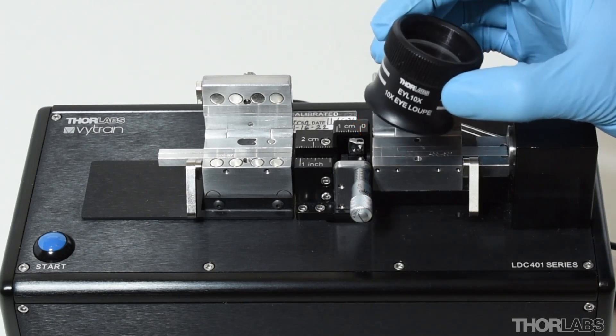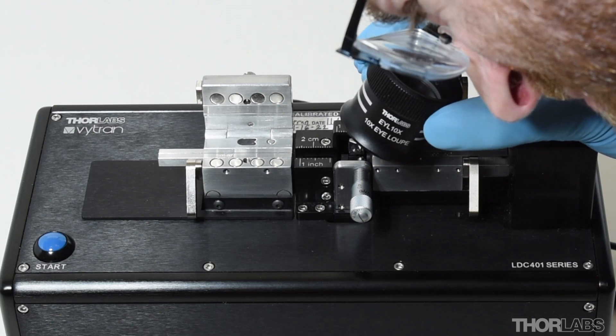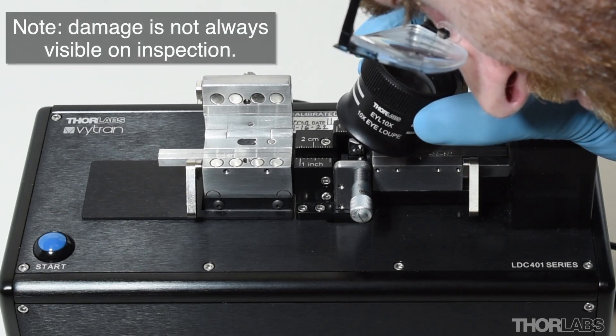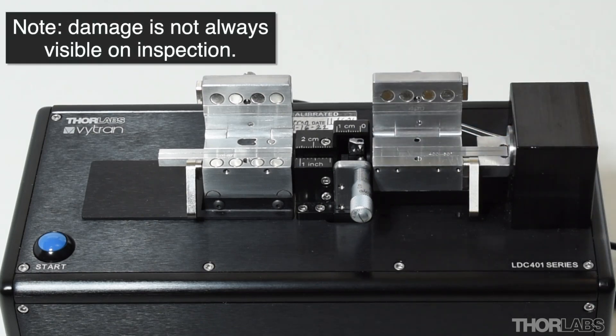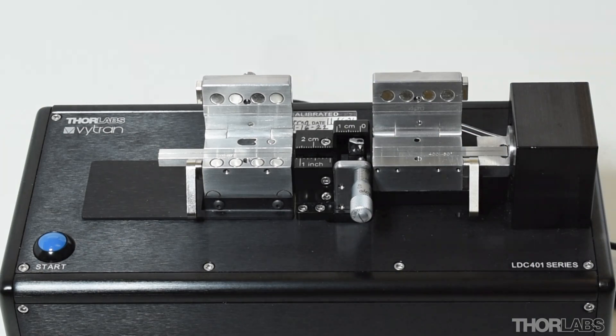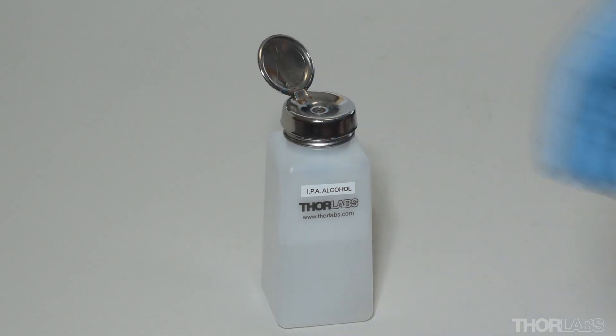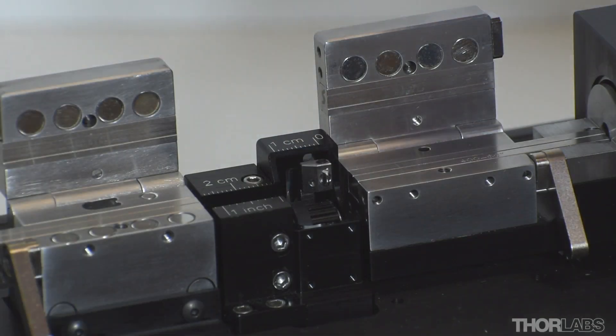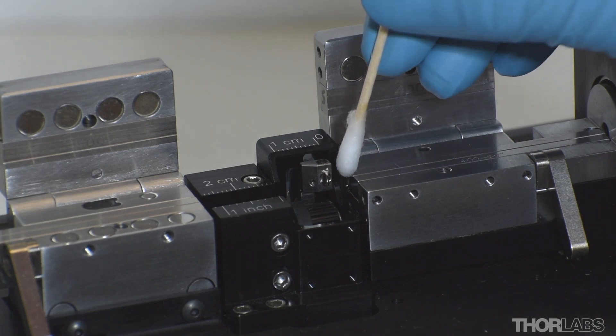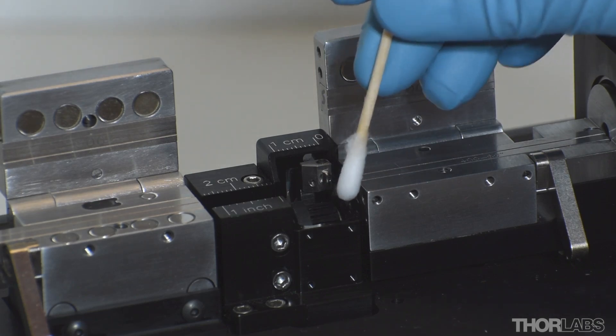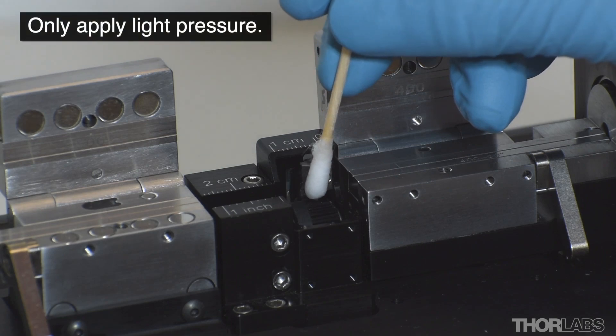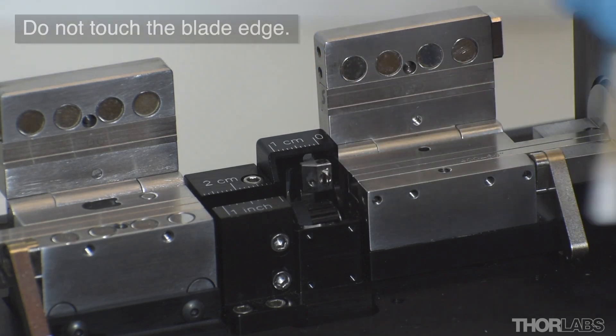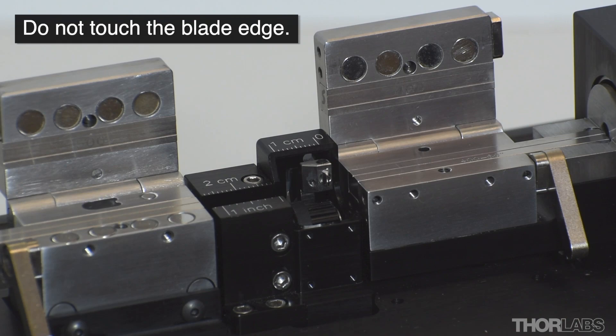Use the eye loupe to inspect the blade for damage. However, it should be noted that even if the blade edge is dull or damaged, it may not be possible to see this. If there are no obvious signs of damage, clean the blade using a cotton-tipped applicator soaked in acetone or IPA. Wipe both sides of the blade, moving the applicator from the back towards the front. Never across the blade edge. Only apply light pressure and do not touch the front edge of the blade using hard metal objects.